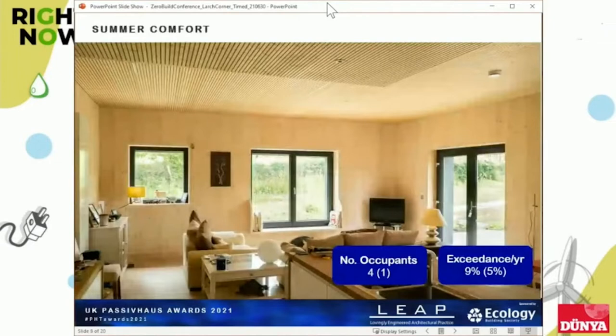In terms of summer comfort, overheating is a key consideration, or avoiding overheating, I should say, is a key consideration in passive house design. I took some very pessimistic views in terms of the amount of opening of windows to keep the building cool because of the concerns about harvest flies and other things, because we're in quite a rural location. And PHPP suggested that we might exceed 25 degrees Celsius for perhaps 9% of the year. But in practice, what we found was it exceeded 25 degrees Celsius for 5% of the year.